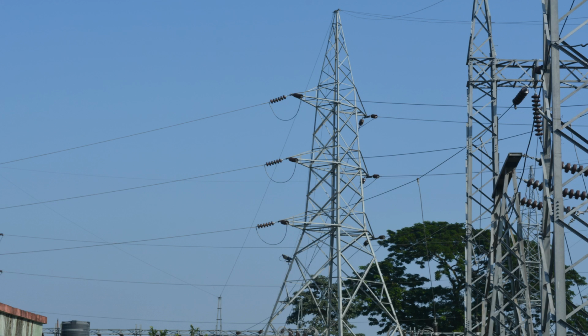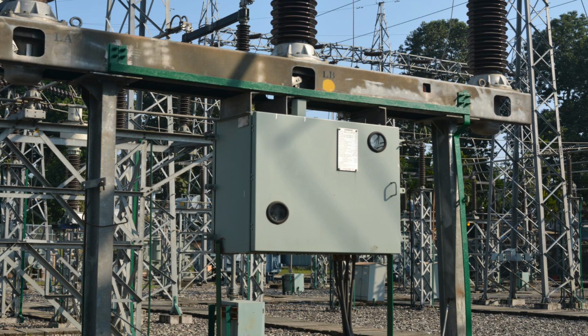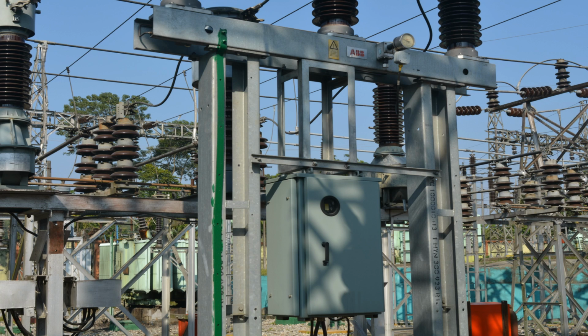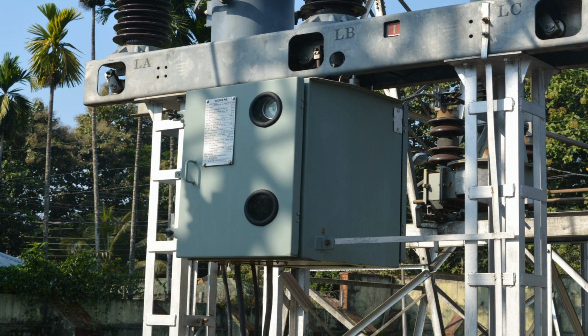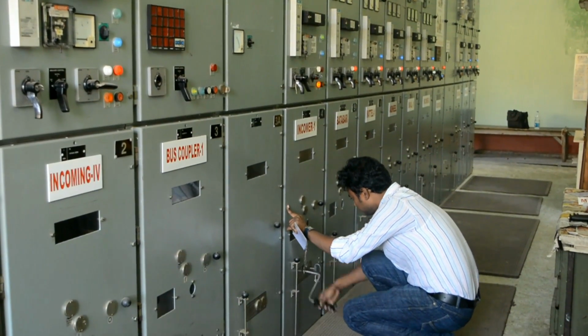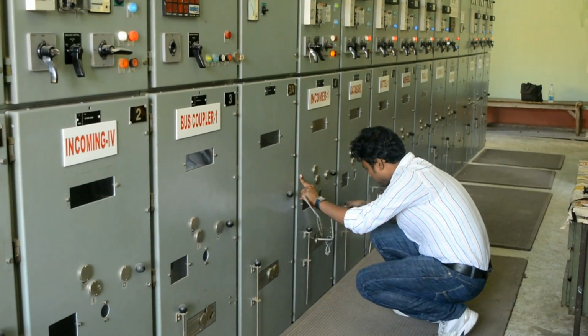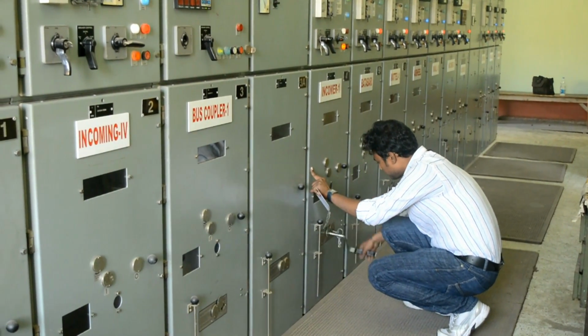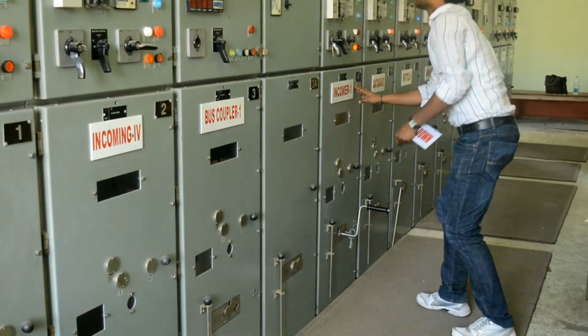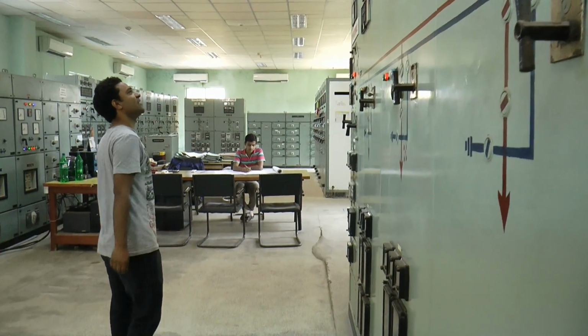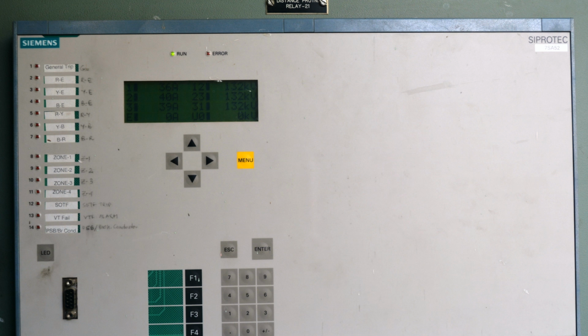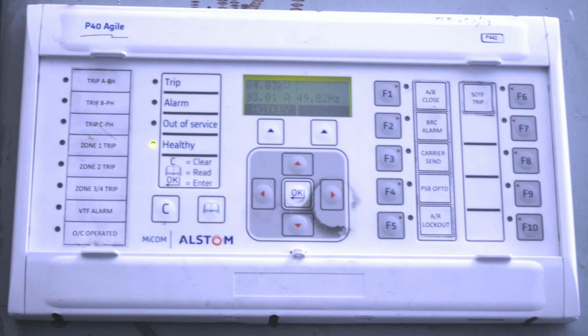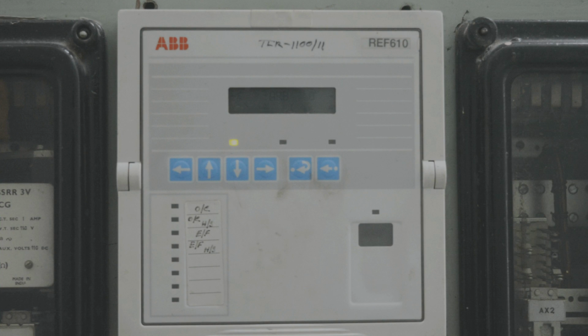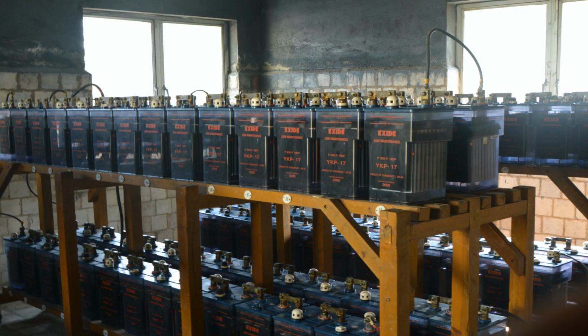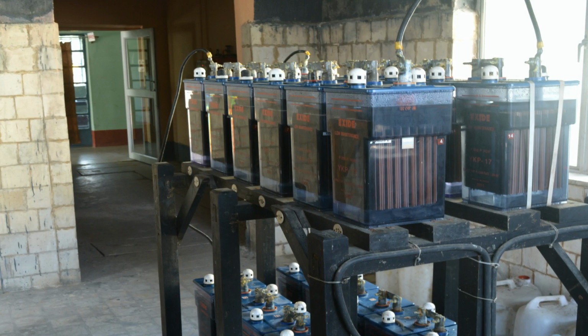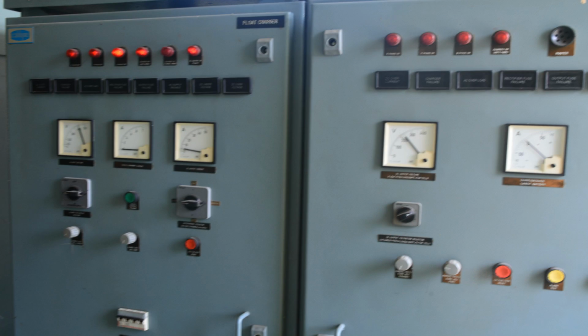In view of catering uninterrupted and reliable power supply, all the age-old 66 kV MOCB circuit breakers have been replaced by SF6 circuit breakers. The 11 kV MOCB breakers are replaced by VCB breakers. For modernization and improvement of system protection, numerical relays have been installed. The auxiliary supply of 220, 110, 48 and 30 volt DC is fed by well-maintained battery bank and battery chargers.